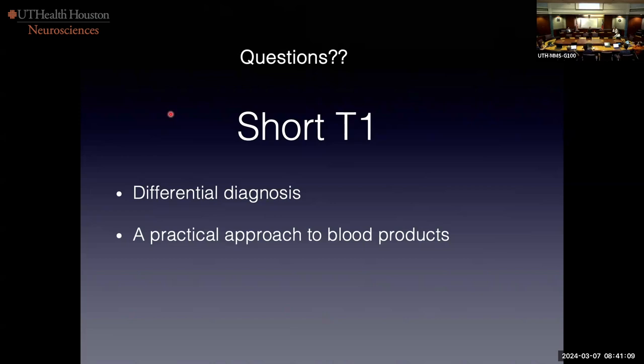We keep coming up with new things every day. Right now, I think we're headed toward running one sequence and then using AI to reconstruct every single possible other sequence you wanted. Then we'll do multi-parametric or bolus GAD — we'll get flow data, spectroscopy data — feed huge amounts of data into the computer, then have a model, maybe a convolutional neural network, to classify. Deep learning is already being used in the magnets — it's called Air Recon. We've been able to use AI to reduce the filling of k-space in half, going from sequences that were six minutes to two and a half minutes.